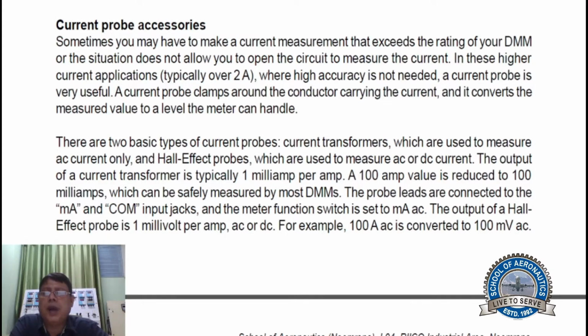The output of a current transformer is typically 1 milliamp per ampere. A 100 amp value is reduced to 100 milliamps, which can be safely measured by most DMMs. The probe leads are connected to the milliampere and COM input jacks, and the meter function switch is set to milliampere AC.